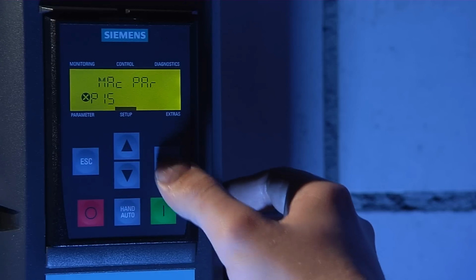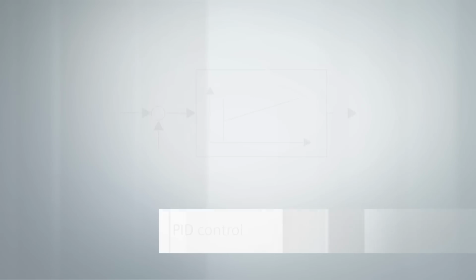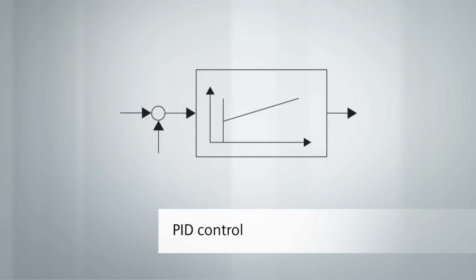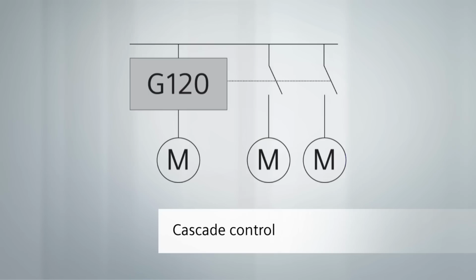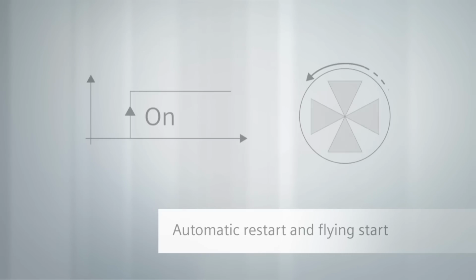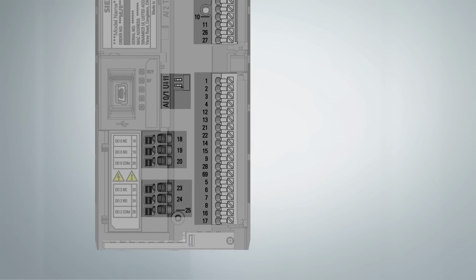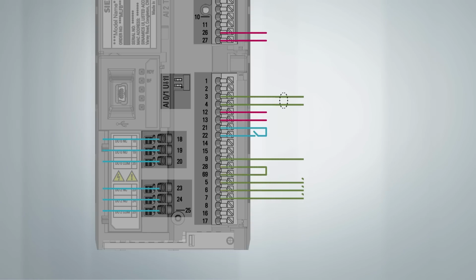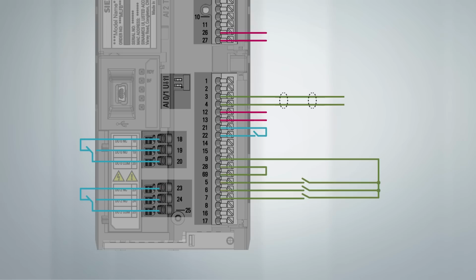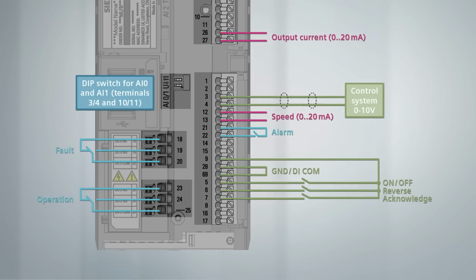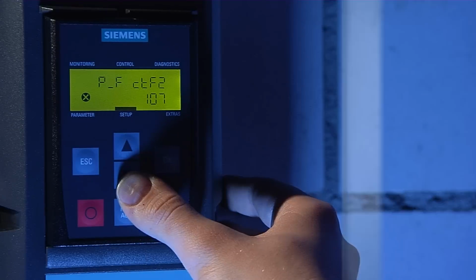The control unit of the G120P has a large set of I/Os and a wide range of software functions to cover all common HVAC solutions. For the most common setup scenarios, the control unit offers predefined programs known as macros. When selecting a macro, the following happens. The I/Os of the drive are automatically assigned to a certain functionality. Certain parameter values, for example the parameters for an automatic restart, are automatically set so that this function is activated without further need for configuration.